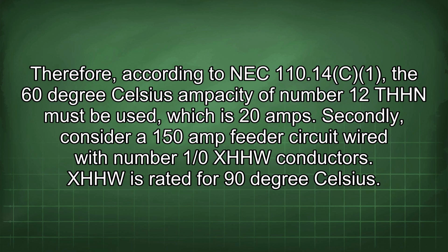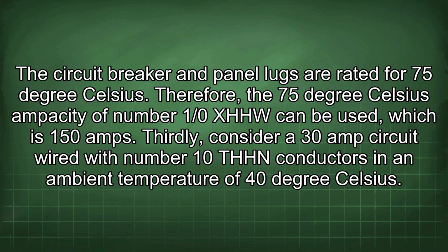Secondly, consider a 150 amp feeder circuit wired with number 1/0 XHHW conductors. XHHW is rated for 90 degrees Celsius. The circuit breaker and panel lugs are rated for 75 degrees Celsius. Therefore, the 75 degrees Celsius ampacity of number 1/0 XHHW can be used, which is 150 amps.